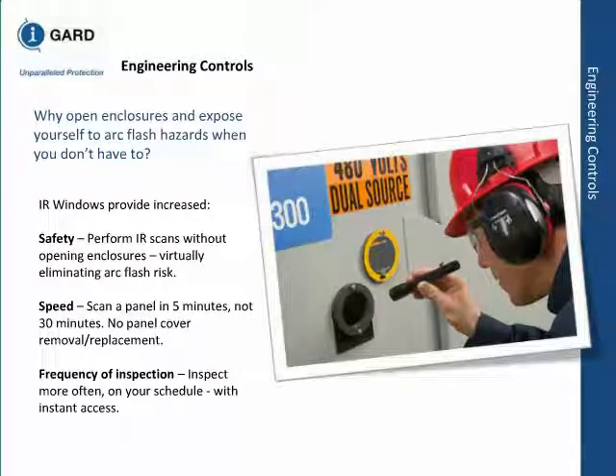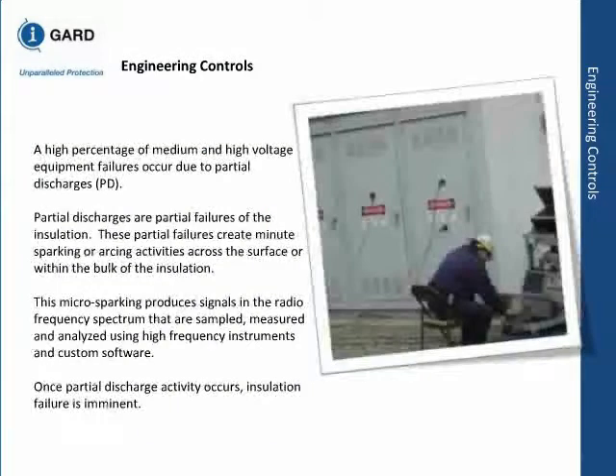In high voltage, the first thing that will happen is a breakdown of insulation, which results in partial discharge or corona. There is a failure of the insulation, and infrared and partial discharge are both based on that. If you can catch it before it goes to fault mode, you have minimized your interruption. So if partial discharge activity occurs, that means insulation failure is imminent. Now technology is available that can almost predict how much time you have. This has been very extensively used for medium voltage switchgear and motors.